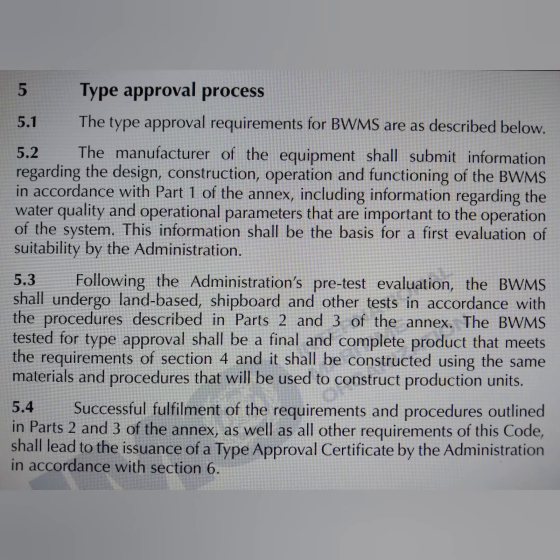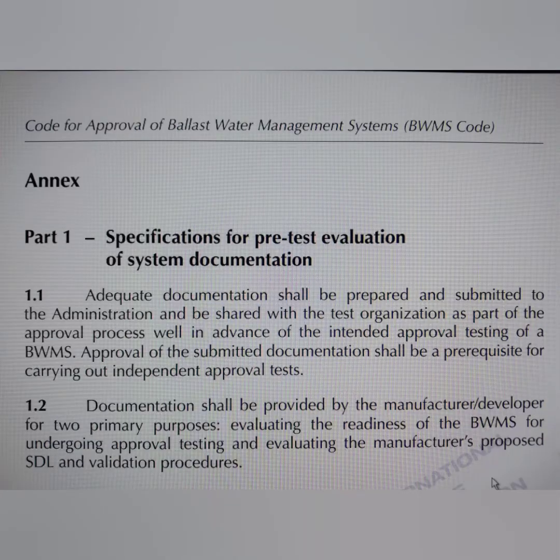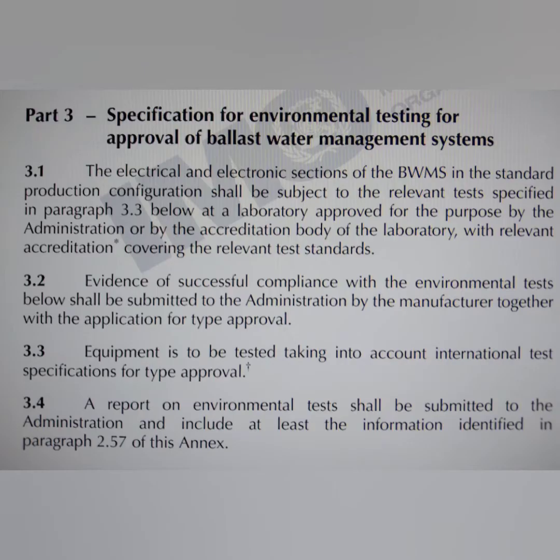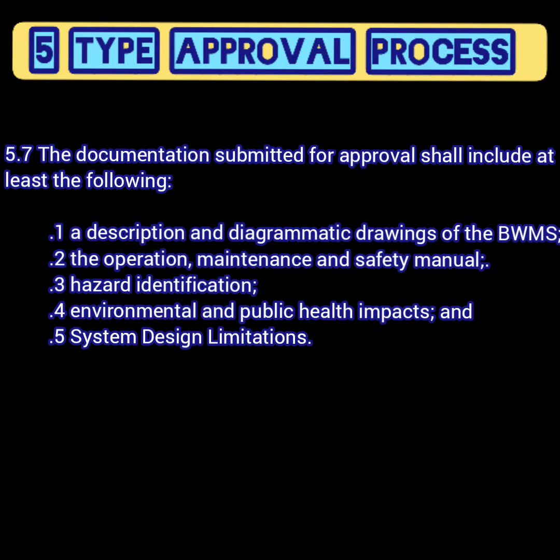Chapter 5 is the type approval process. As the name suggests, it tells you how to get approval for the ballast water management system, and it gives reference to parts 1, 2, and 3 of the annex. Part 1 is specifications for pre-test evaluation of the system documentation; part 2 is test and performance specification for approval; part 3 is specifications for environmental testing for approval. There are five documents required to be submitted: first, description and diagrammatic drawing of the system; second, operation, maintenance and safety manual; third, hazard identification; fourth, environmental and public health impact; fifth, system design limitation.